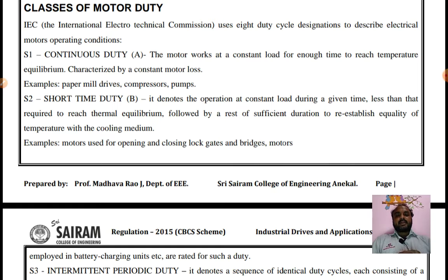Next, short time duty. Some of the drives are used for a short, specified time, and those drives come under short time duty. It denotes operation at constant load during a given time less than that required to reach thermal equilibrium, followed by a rest of sufficient duration to re-establish equality of temperature with the cooling medium.